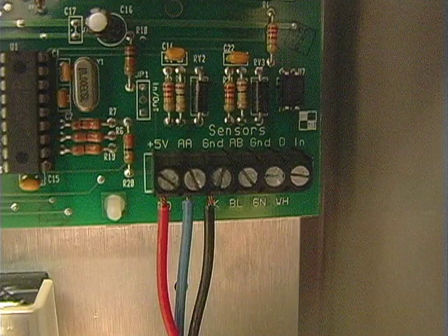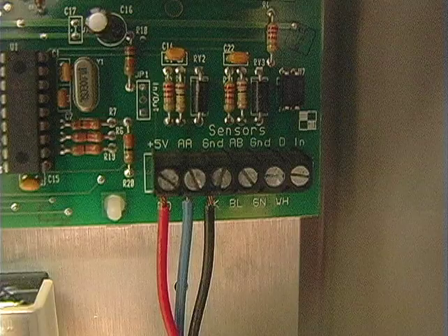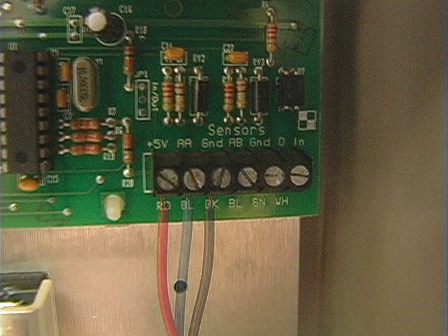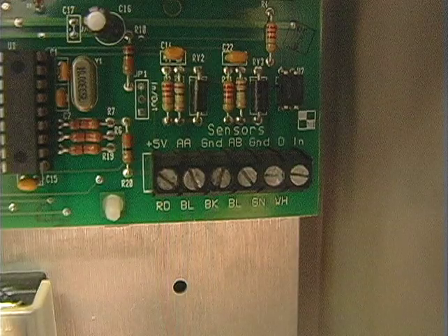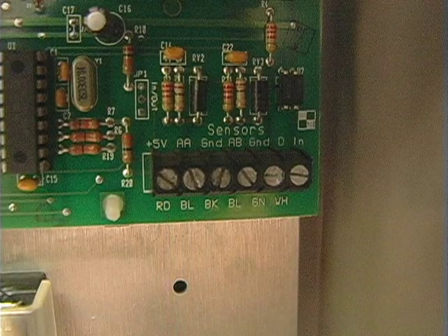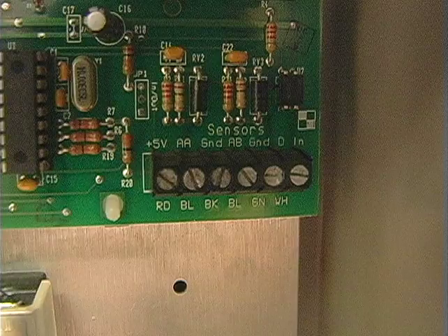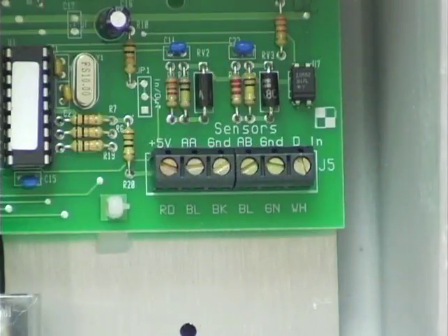One of the most common problems that you'll have with this control panel is the electrician doesn't hook up the black, blue, and red wires in the corresponding slots where they're supposed to. Looking at the control panel from left to right, it's supposed to be red, blue, and black, the BL being blue and the BK being black. And I've gone out numerous times and they'll install it red, black, blue.